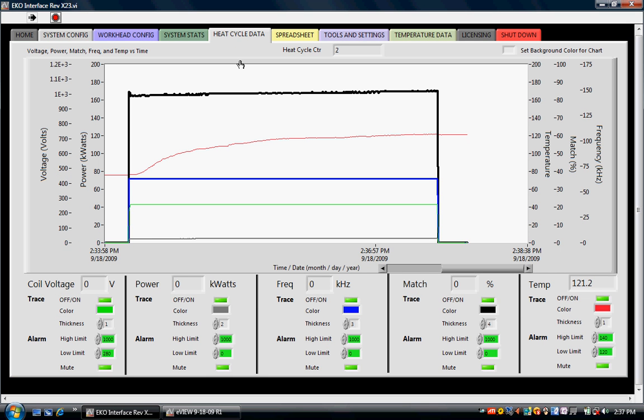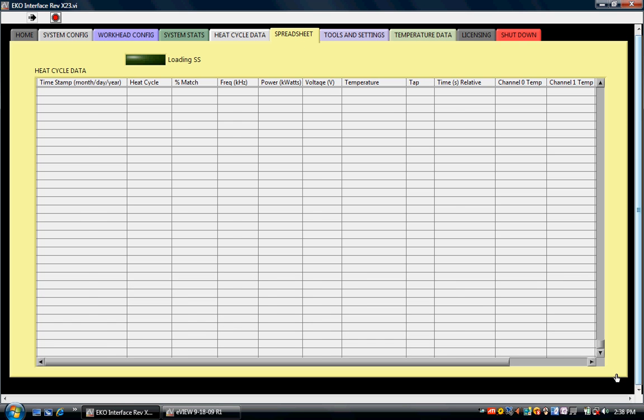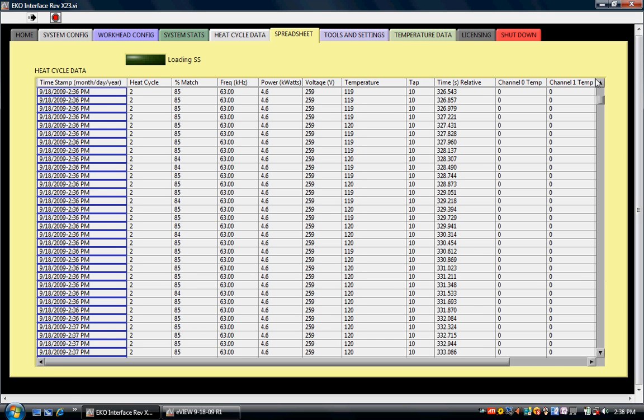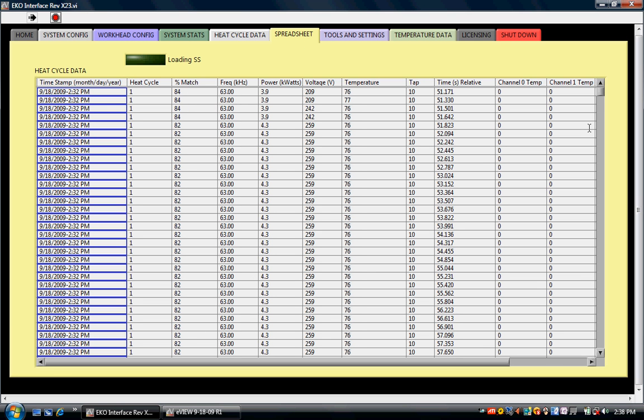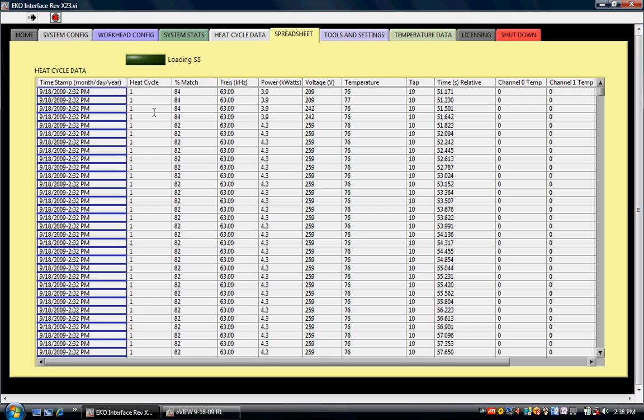One of the most valuable features of eView is the ability to spreadsheet the information from our induction heating processes. The spreadsheet can be viewed from inside eView. This is all the information that is shown graphically in the heat cycle data page and the temperature data page, all compressed into a spreadsheet. All the entries are time stamped and date stamped. They are grouped by heat cycle numbers. Every time the heat is turned off and turned back on, eView increments a heat cycle counter so that we can link heat cycles back to the parts that were actually treated. If the operator knows the order that they ran parts, they can actually link the data in the spreadsheet to individual parts.